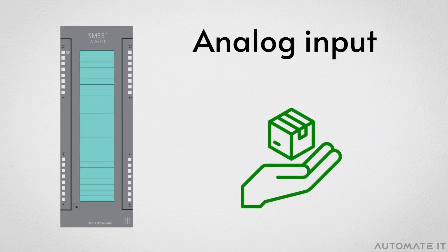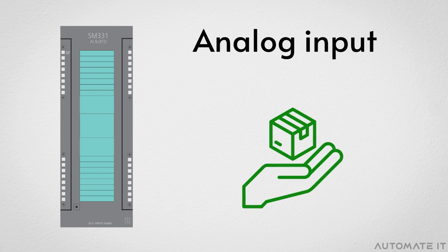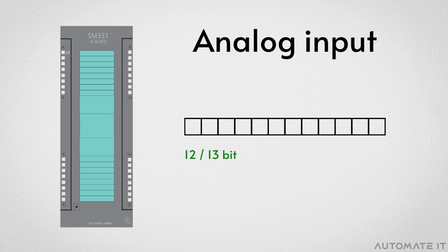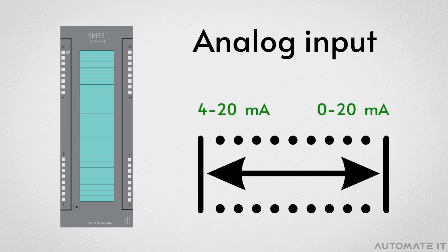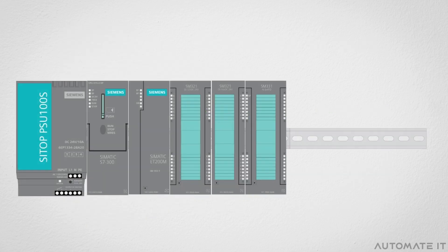Analog input modules are also used to receive data. In this case, 12-bit or 13-bit signals are used. Their normal operating ranges are from four to 20 milliamps and from zero to 20 milliamps. They are in the sixth position on the rack.